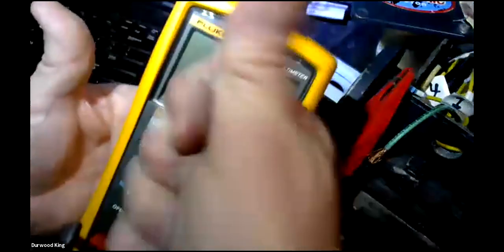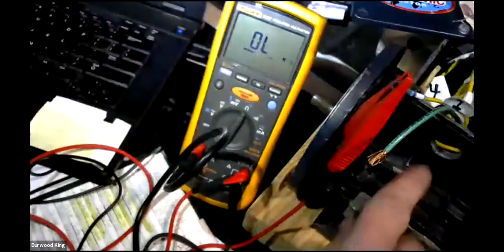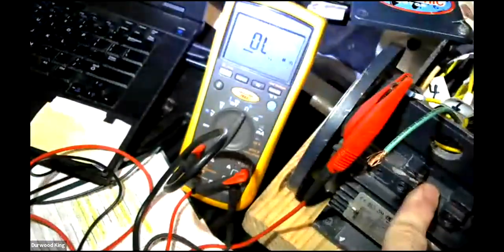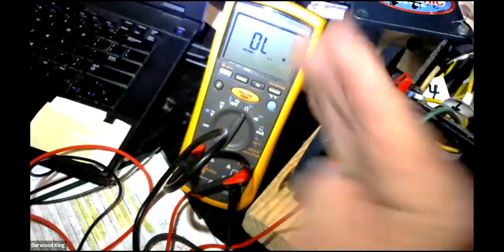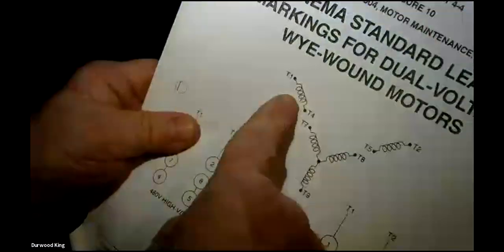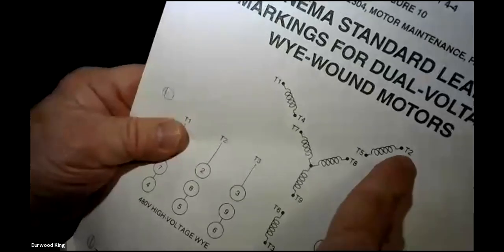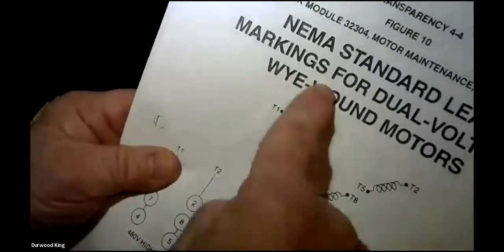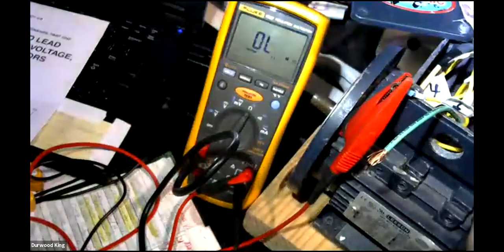60 meg is the range on that resistance. OL, so it's beyond that. So that means that you have a broken winding in the motor, because you should actually be reading through that Y connection. If you look here, right now, you should be getting a resistance reading from here to here. Okay, you follow? Yes, sir. Yeah. But you're not getting it. You're getting an open circuit inside that motor. That motor's actually got a broken winding or burned open on the inside.